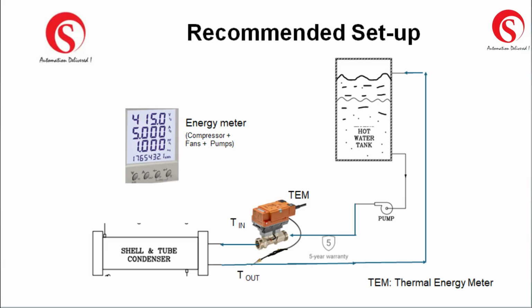I prefer to use shell and tube condensers because they are very easy to descale. The way you may be maintaining some of the big chiller plant water cooled condensers by descaling them using your regular scheduled maintenance, in a similar way you will be able to maintain the shell and tube condenser of a hot water heat pump also. And then it will have an expansion valve and all other standard refrigeration accessories in the system. It will have a circulation pump, taking the hot water from the storage tank, passing it through the shell and tube condenser, and giving it back to the thermal storage tank.